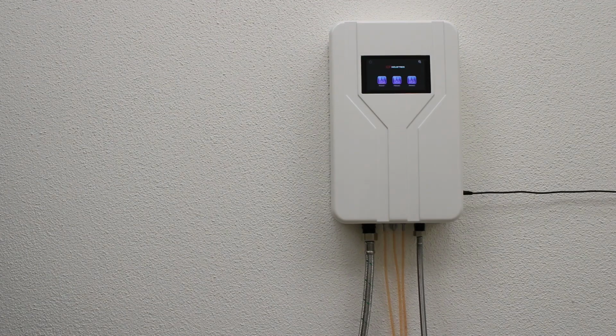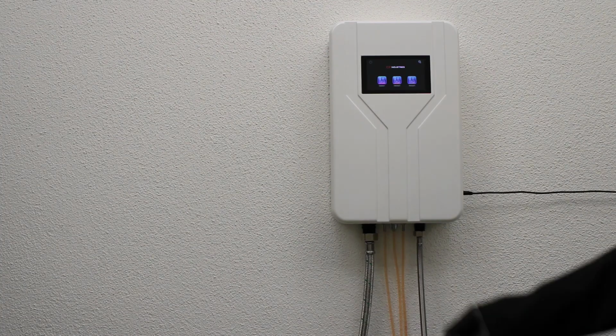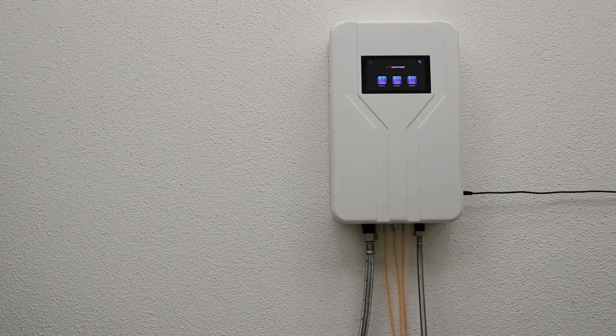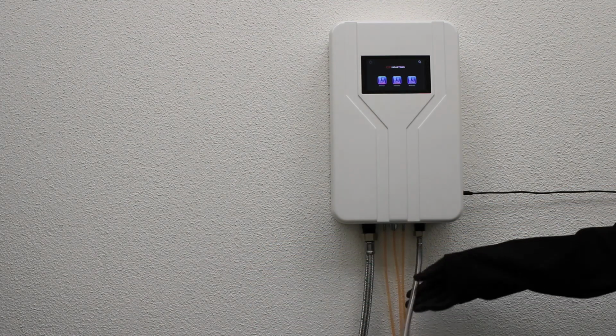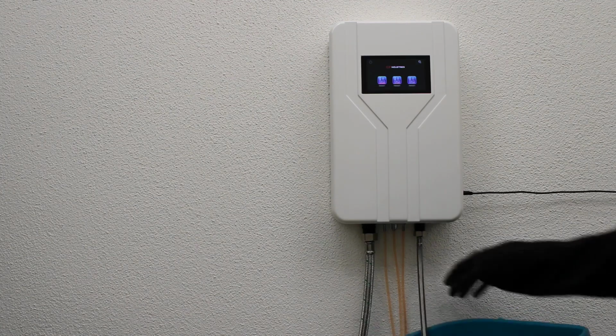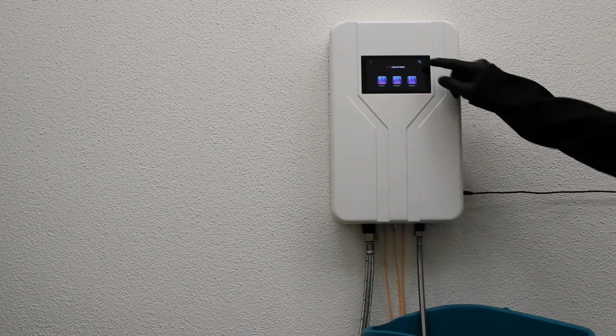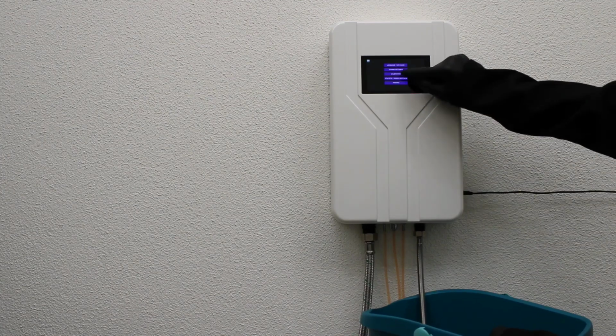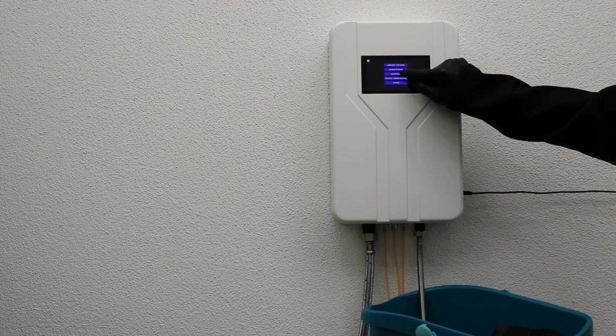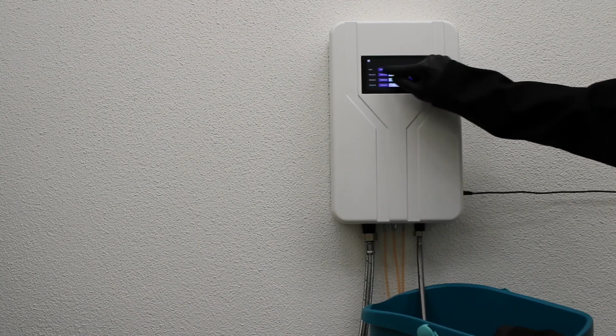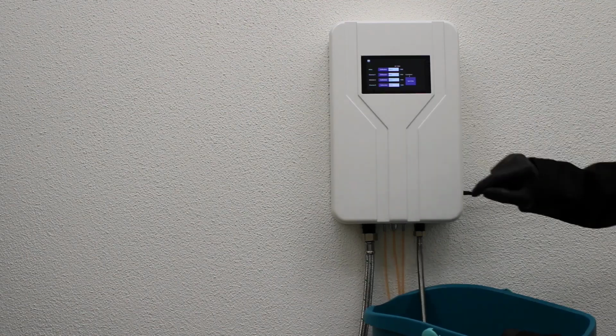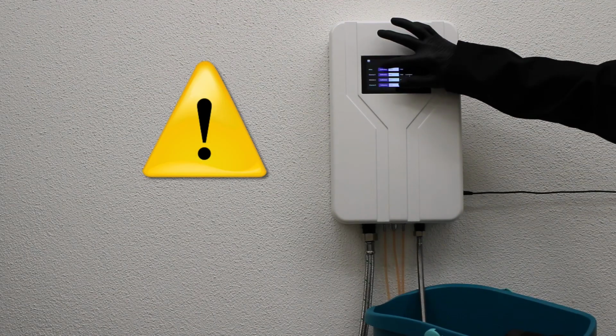Water calibration. To perform the water calibration, you will need a bucket with a capacity of at least 10 liters and a measuring cup with a capacity of at least 1 liter. First, take the bucket and place the output hose of the dosing system into the bucket. Then, press the settings button located at the top right of the display. In the list, you will find the calibration option. In the first line, you will see the calibration for water.